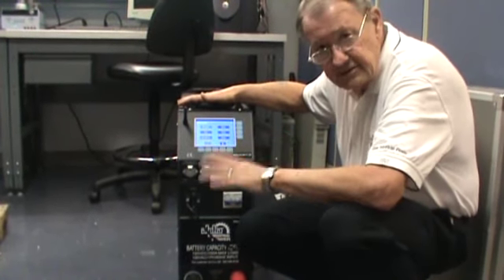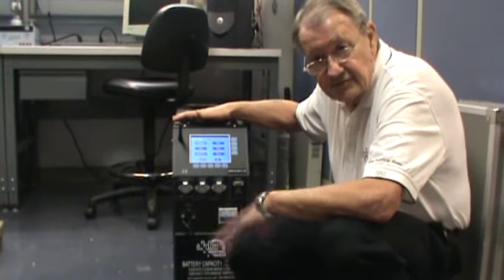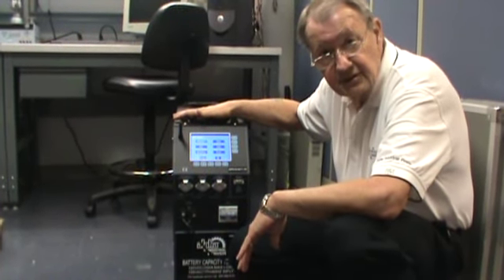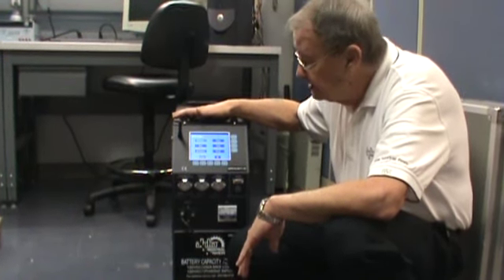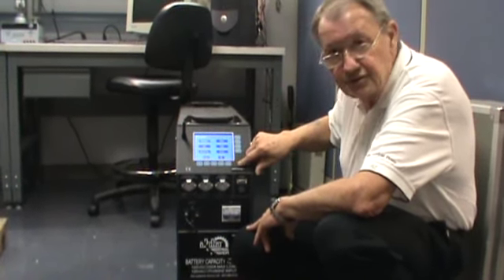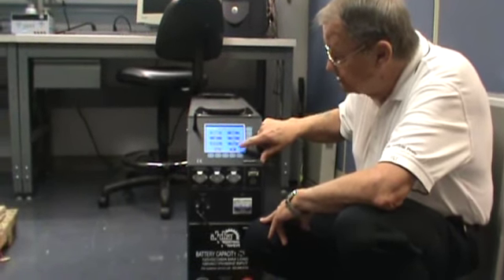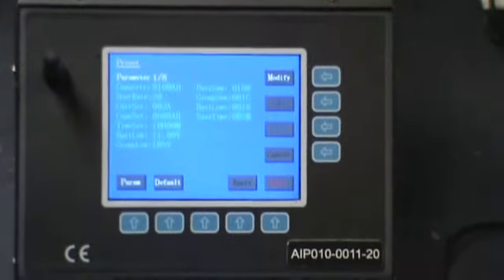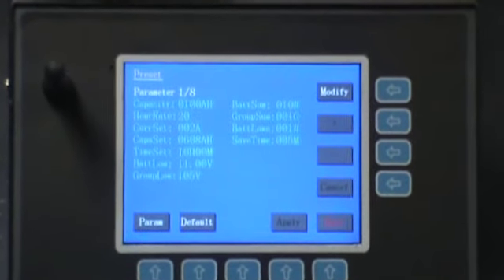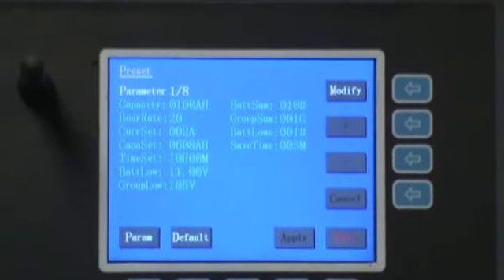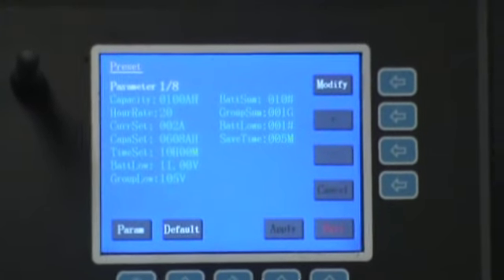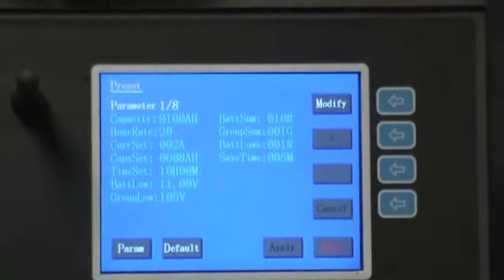The unit basically can do multiple things. The first thing I'm going to talk about is the ability to use it as a standalone load bank, and for that I'm going to walk you through the menu. It's all touch screen. For example, we would normally go to the preset position, select it, and say OK. The unit has the capability of storing up to 8 different settings. So you could set it up for one particular type of battery, and select a second parameter for a different type of battery. So you have 8 possibilities of storing different settings in here.